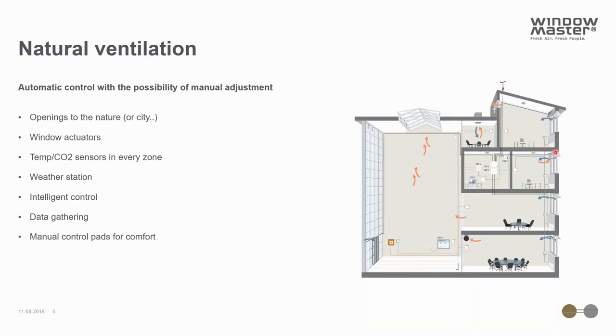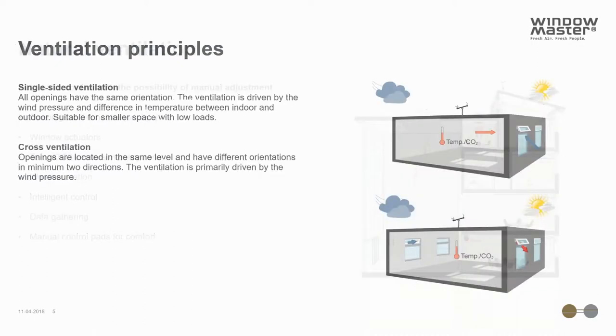But the question is: how much air can you achieve through the window openings that you have for a project? How large an air change rate can you really get? This will of course depend on which ventilation principle you're working with. For the same amount of opening area you can achieve, for example, a much larger air change rate for cross ventilation compared to a single-sided ventilation system. So it's very important to take into account in your calculation which kind of strategy you're using.